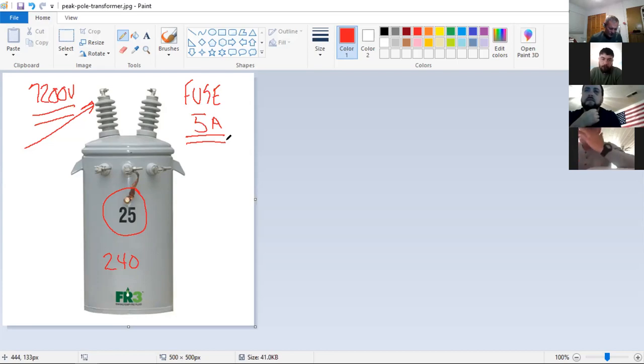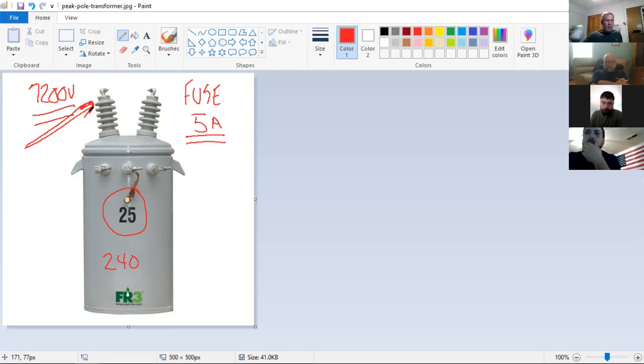And I'll tell you, when you get out there in the world, you're usually just going to carry a chart around with you in your pocket. And after what, Robbie? Yeah. 2, 3, 4 months, you're going to say, that's a 25. My input voltage is 7,200. I just know that from my system. That's a 5 amp fuse. That's right. Just going to learn that in the process. A lot of guys I used to work with, the younger guys coming in, they always took their hard hats and took a permanent marker and wrote fuse sizes inside their hard hat. That'll work too. Yeah. So, back in the old days, when you hired, and not to say anything bad about contractors, contractors would come into an organization, brand new hires and whatnot.